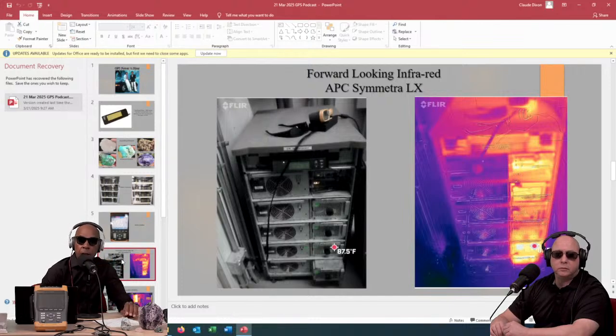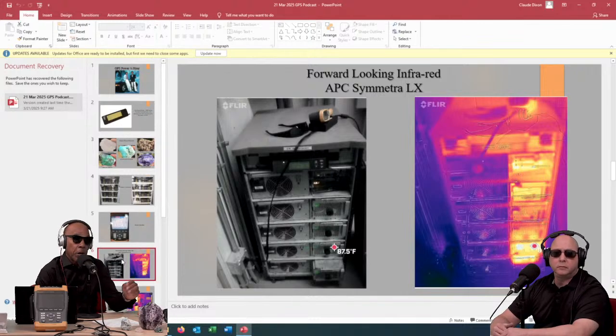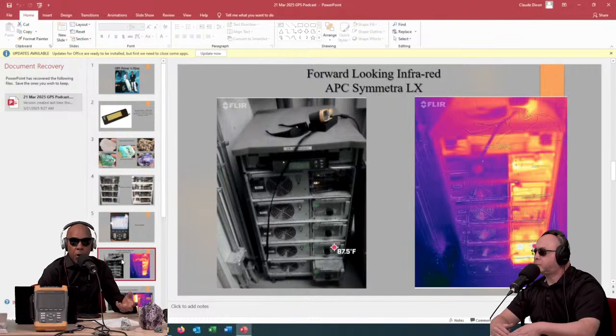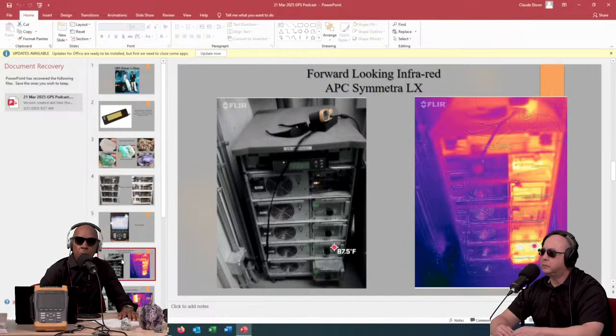I've seen them so swollen you have to use a pry bar to break them up to get them out of the module. No one wants to see that, but that's one of the beauties of this camera - you can see it before it happens and take corrective action. This is another service we sell in the field: thermal imaging, not just of the UPS but circuit breaker panels, air conditioning equipment, anywhere energy is going through a machine. This camera is very, very valuable.